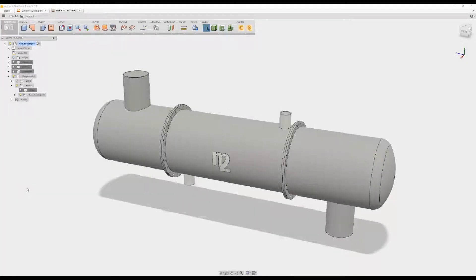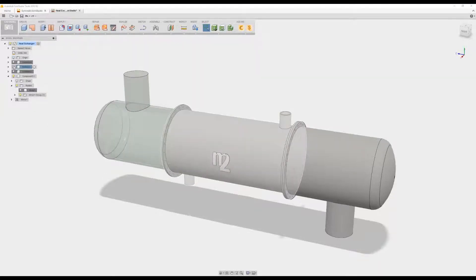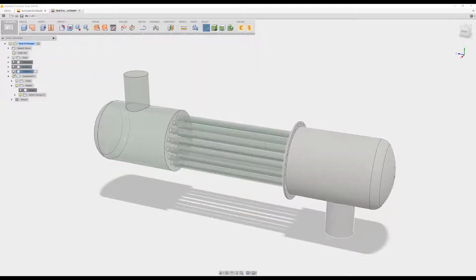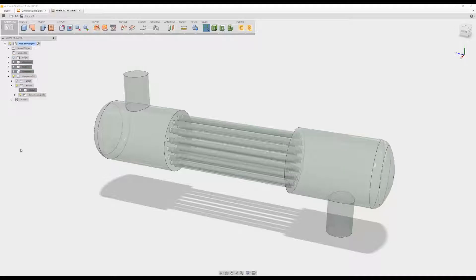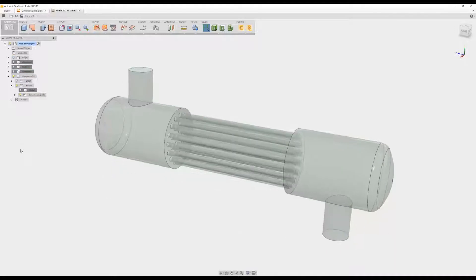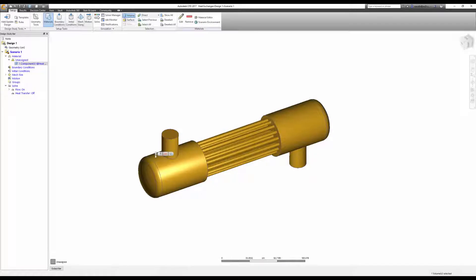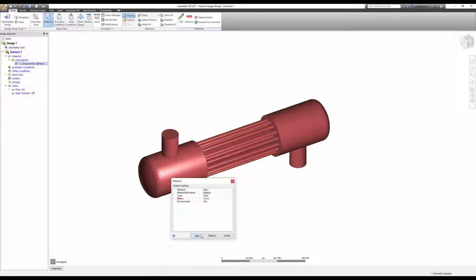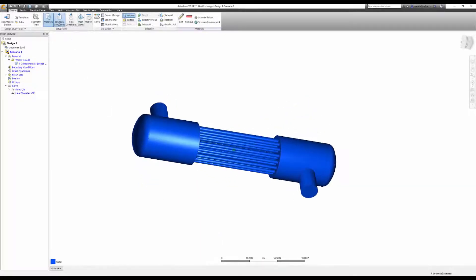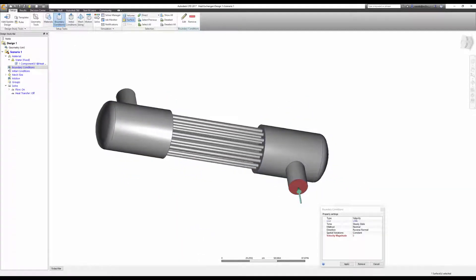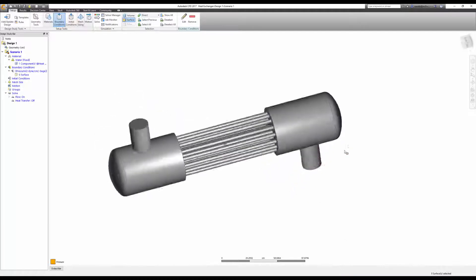For the sake of this video, I'll launch both a whole model and a divided one to compare them. Let's keep it simple — I'm only going to solve for internal flow, so all I need is the internal volume. I'll assign water to it, I'll assign zero pressure at my outlet, and a volume flow rate of 1000 gpm at my inlet.